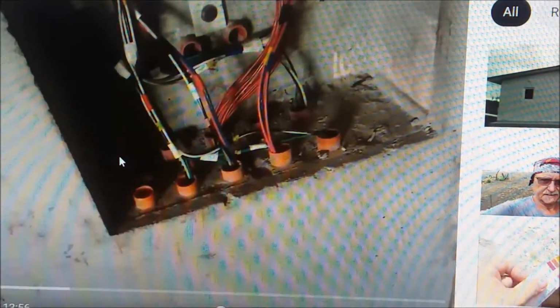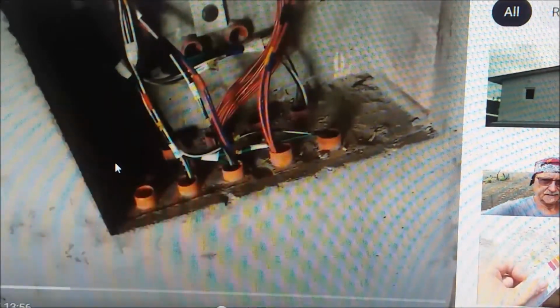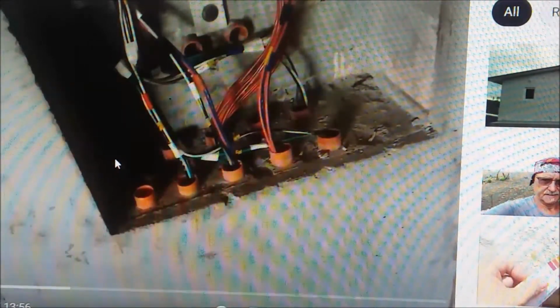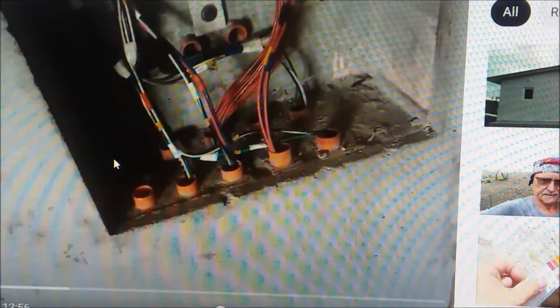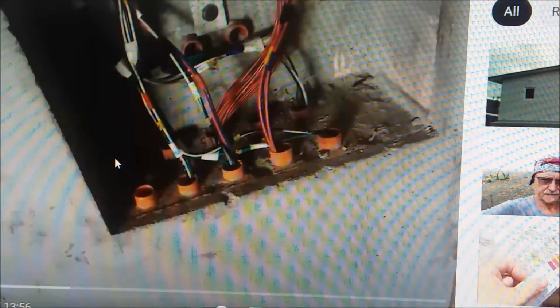Now I've got breakers I can take down to 1.3 amps if I want. If I wanted to put in like 6 LED light fixtures, the kind used locally, with a total draw of about 4 amps, I could put a 5 or 6 amp breaker in. These are actually fuse holders, not breakers—I could have gotten breakers from the same place.